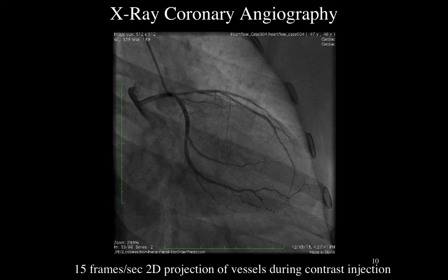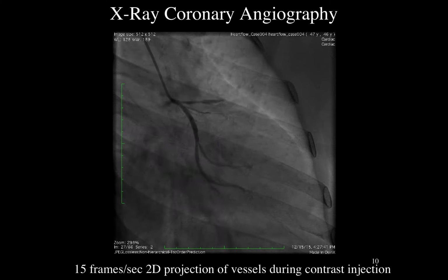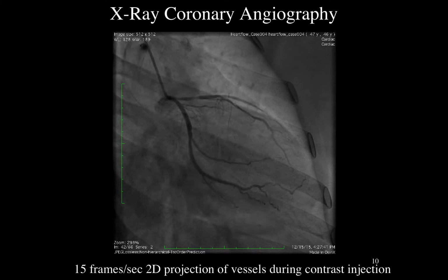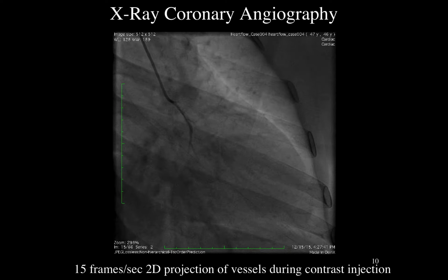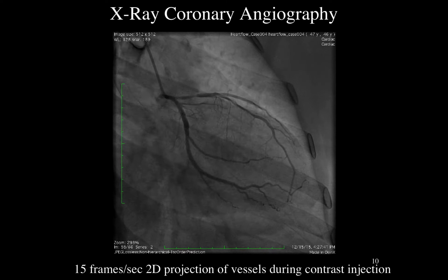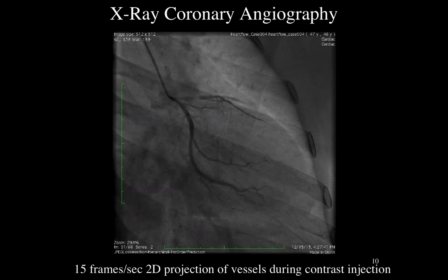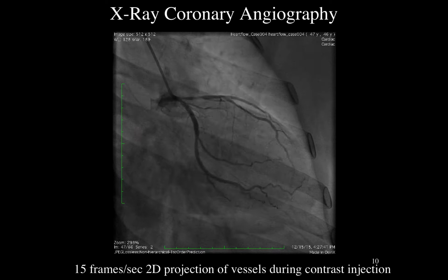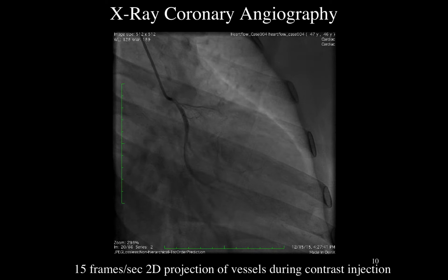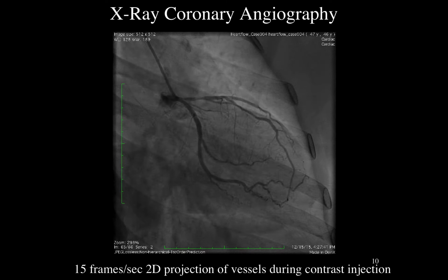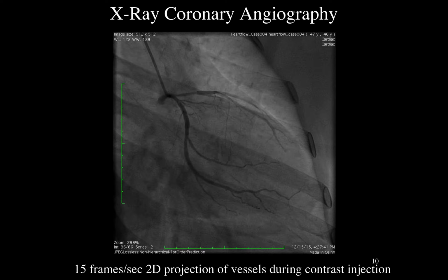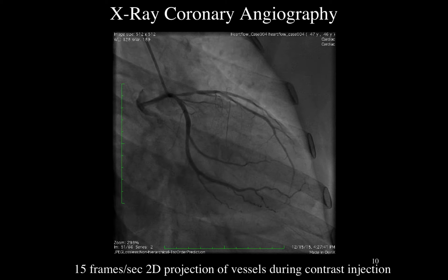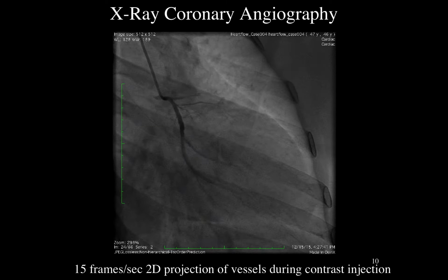The reason these pictures look really clear is that the detector itself is a high-resolution detector. The X-ray source itself is a very high-resolution source. The X-rays are coming from basically a tiny little spot and shining through the patient, and they're being strobed so that the exposure for each frame of that movie is only 50 microseconds or something. So they're really fast pictures. The shutter speed is very, very fast. And so you get nice, clear pictures. And this technology has been developed over the last 80 years, and it just gets better and better and better.